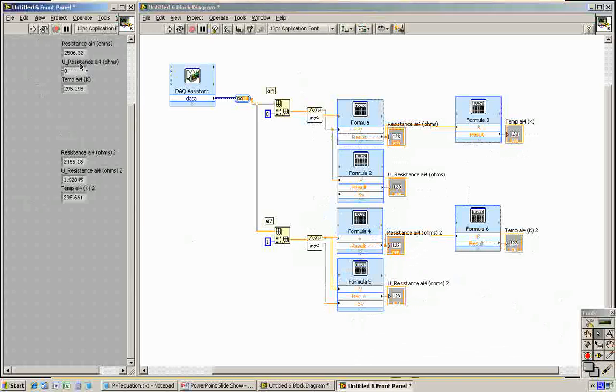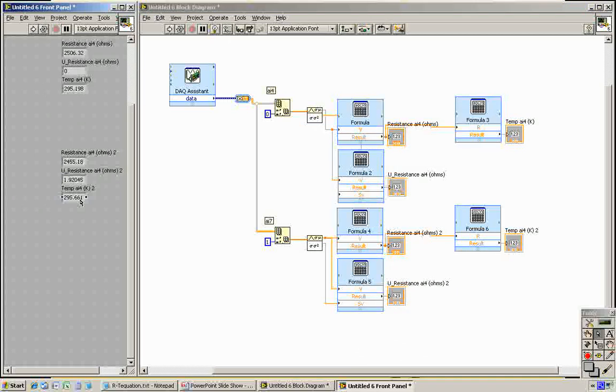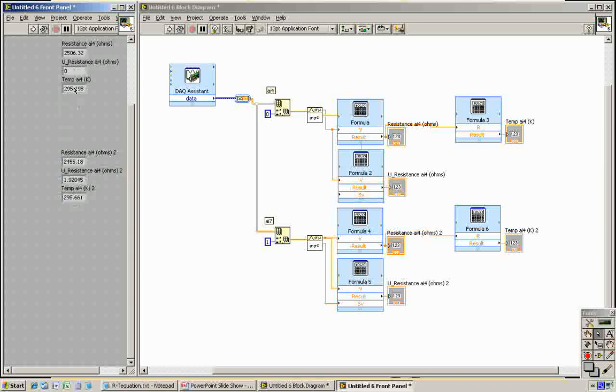We see that they measure a little different resistances. Uncertainties are both small, less than a tenth of a percent. And they measure the temperatures different here by about half a degree K, which is more than one percent error. So that shows you that there's some bias error in here that we aren't accounting for that's pretty big. And the precision error for each of these is pretty small. So if we were to calibrate these, we could eliminate this bias error and get the resistance down the same. These both should measure the same thing. They're sitting right next to each other in the room.